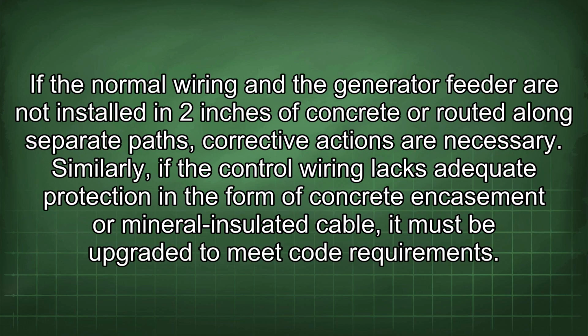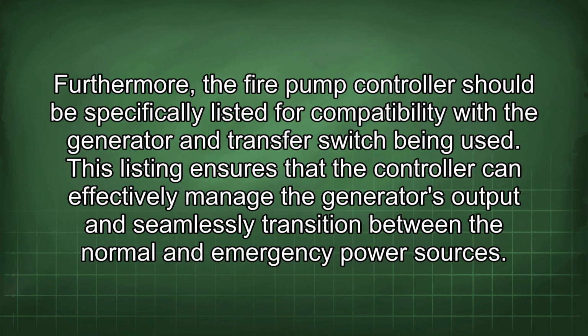If the normal wiring and the generator feeder are not installed in 2 inches of concrete or routed along separate paths, corrective actions are necessary. Similarly, if the control wiring lacks adequate protection in the form of concrete encasement or mineral insulated cable, it must be upgraded to meet code requirements. Furthermore, the fire pump controller should be specifically listed for compatibility with the generator and transfer switch being used.